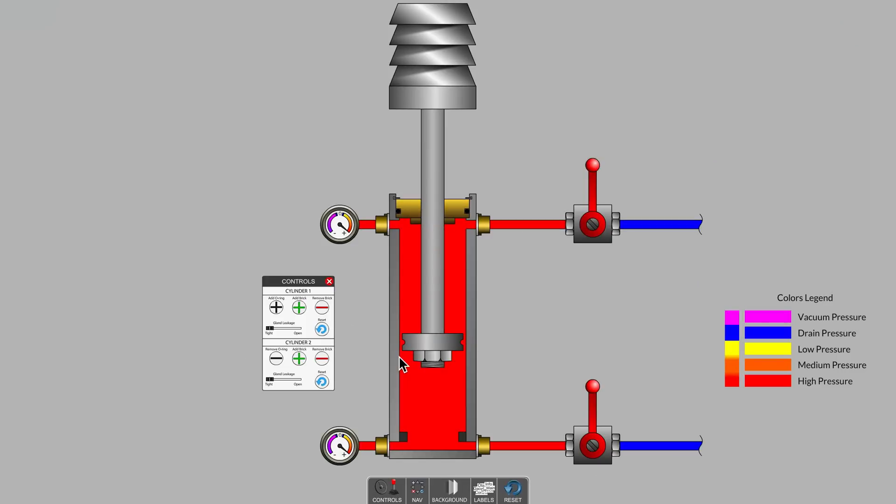I am sure that you did notice additional settling downward when the piston seal was removed. With the piston seal removed and all internal pressures equalized, the surface area on the upper annular part of the piston and an equivalent amount on the bottom of the piston cancel out.